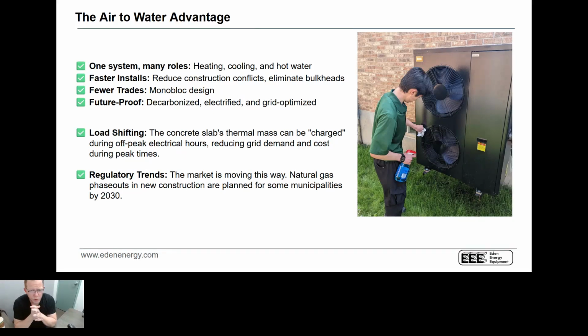So when I was originally talking about air-to-water heat pumps, which goes back many years now, there was a lot of excitement about air-to-waters and a little bit of a struggle of like, how do we use them? How do we deploy them? And when we talk about future-proofing, one of the really cool things about air-to-water heat pumps is utilities really don't realize yet, but they're starting to figure out that air-to-water heat pumps are good for the grid. They're actually better for the grid than some other heat pumps because of how we can utilize them. And specifically, it has to do with load shifting.